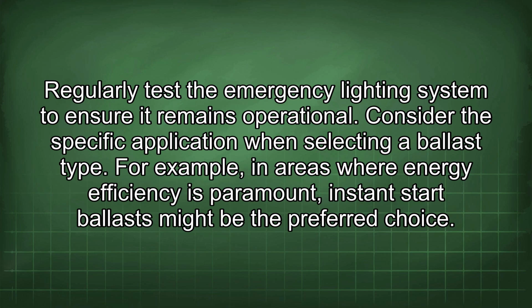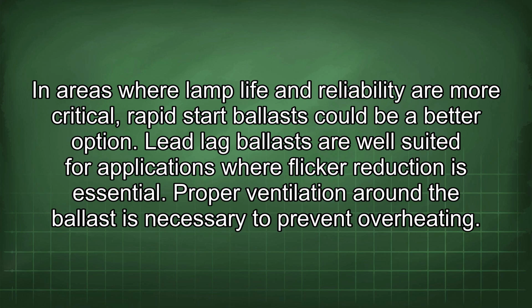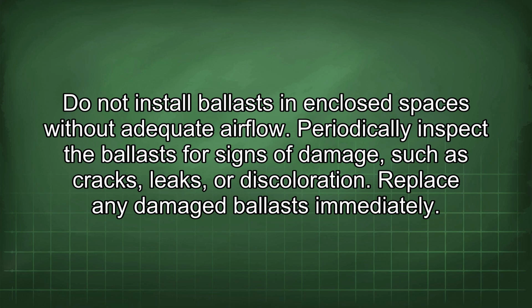Consider the specific application when selecting a ballast type. For example, in areas where energy efficiency is paramount, instant start ballast might be the preferred choice. In areas where lamp life and reliability are more critical, rapid start ballasts could be a better option. Lead lag ballasts are well suited for applications where flicker reduction is essential. Proper ventilation around the ballast is necessary to prevent overheating. Do not install ballasts in enclosed spaces without adequate airflow. Periodically inspect the ballasts for signs of damage, such as cracks, leaks, or discoloration. Replace any damaged ballasts immediately.